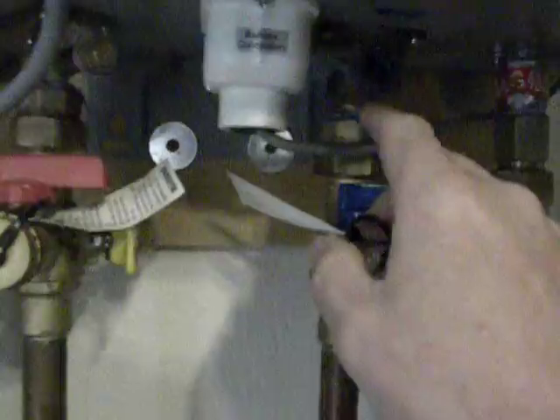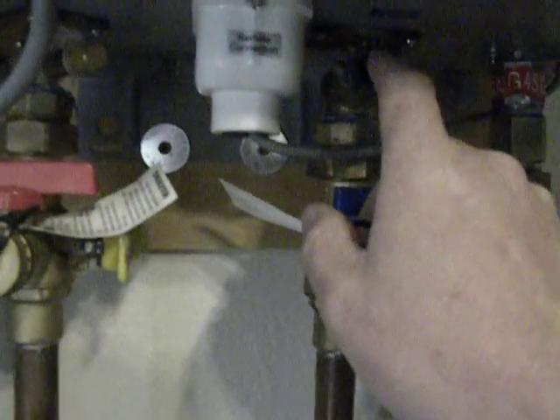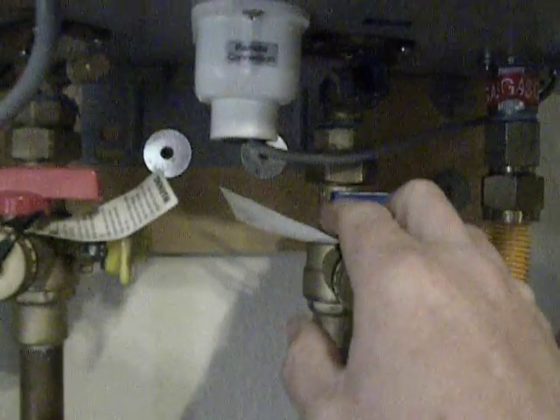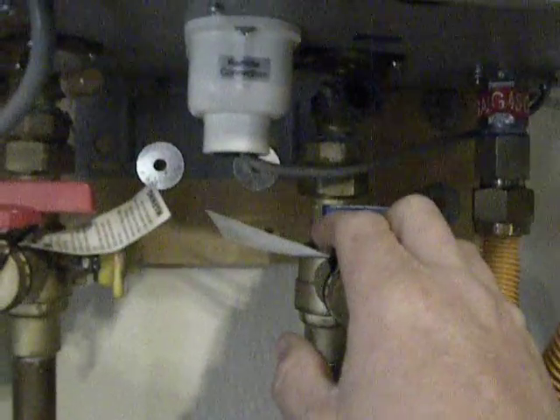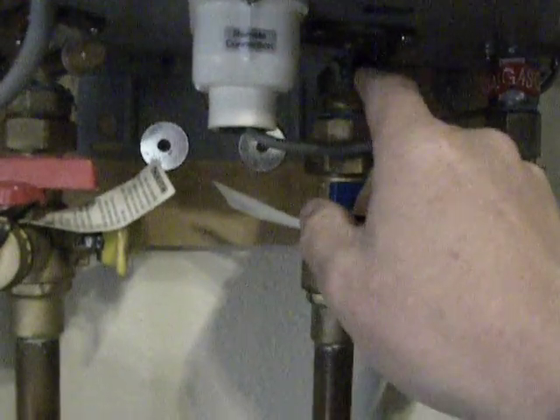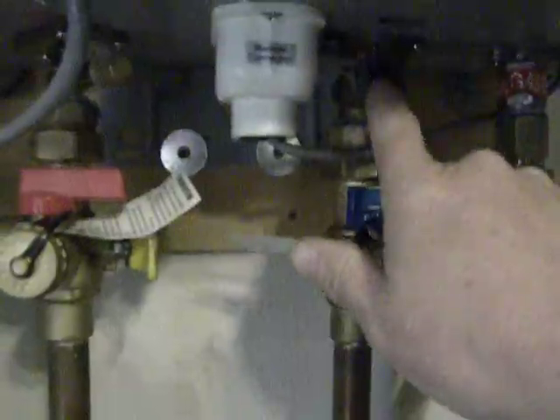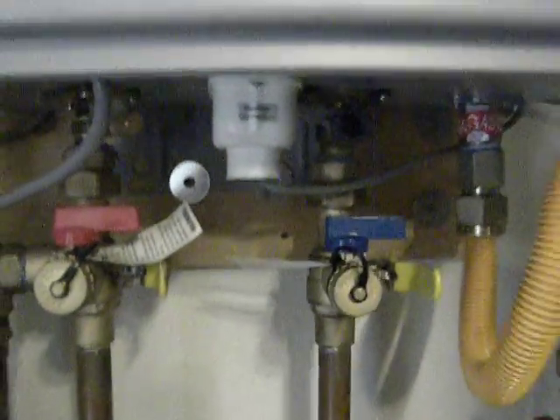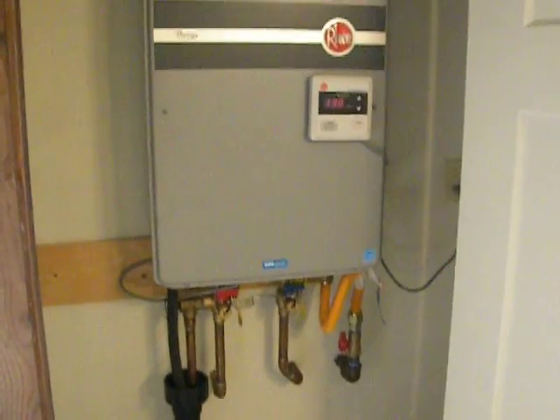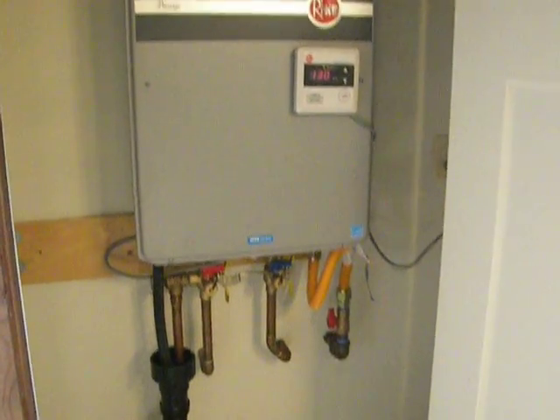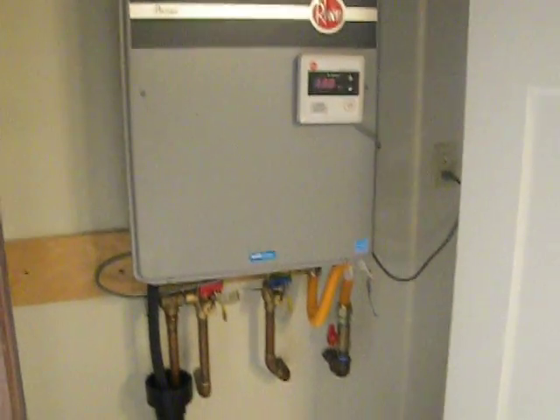If you have a lot of sediment and silt in your water because you don't have a whole house filter, you need to clean this screen about every 60 days until that sediment is no longer pushing through from your well. This is important, because the unit will be ruined in a matter of 2 years if you don't clean it out — that sediment will eventually push through and start messing up the heat exchanger.